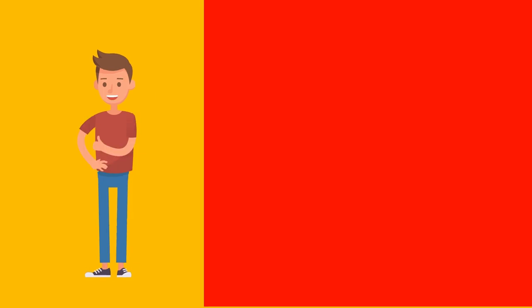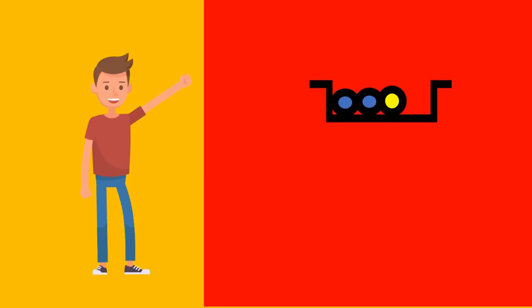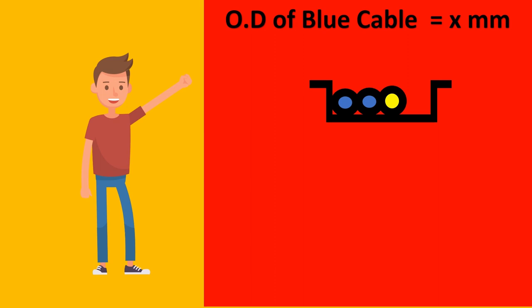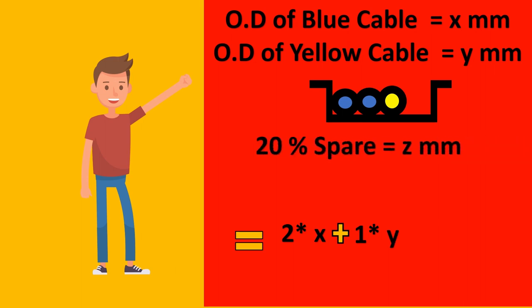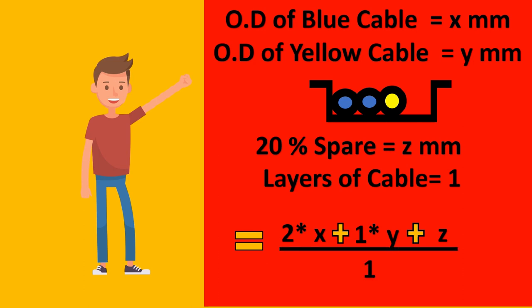Now let's see if Elon understood. It seems he needs an equation. Here's your cable tray: let the OD of the blue cable be X mm and the OD of the yellow cable be Y mm. The calculation is: (2X + Y + Z) / number of layers, where 2X represents two blue cables, Y represents one yellow cable, and Z is the spare capacity in mm. If there is one layer, you divide by one; for two or three layers, divide by two or three accordingly.